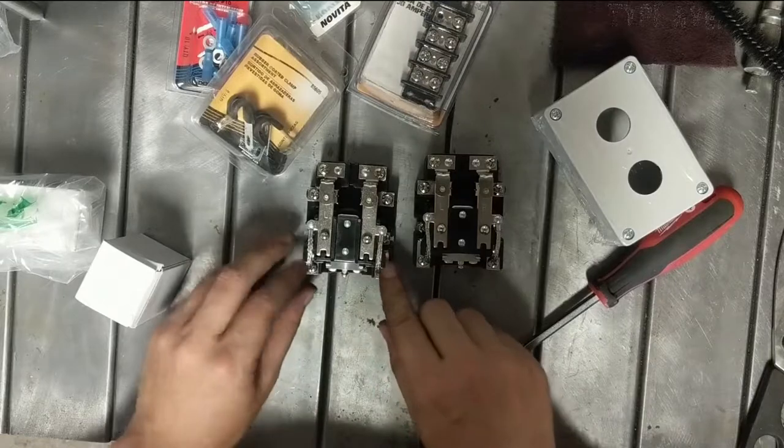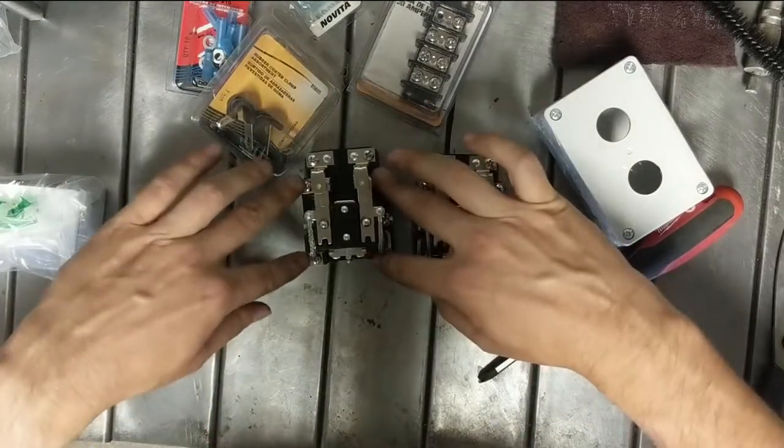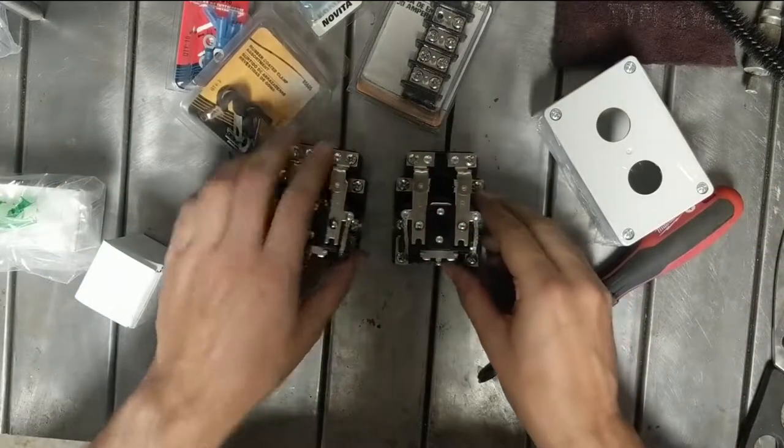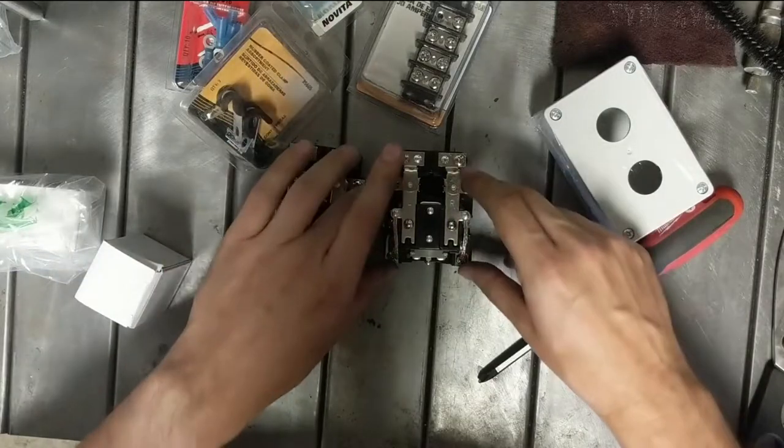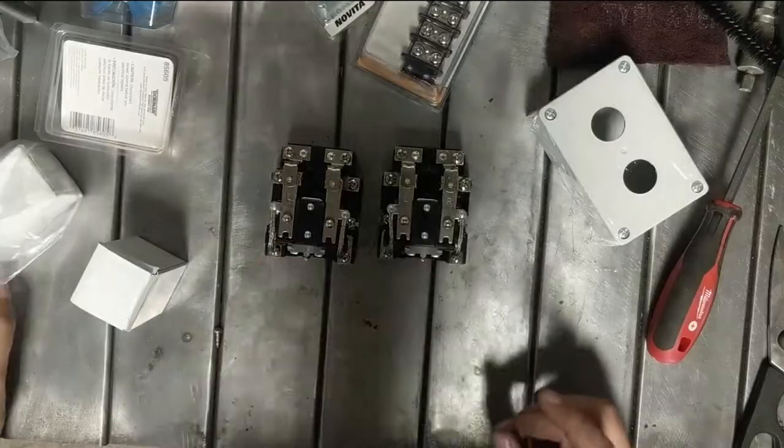What we're going to do is use the normally open contacts on one relay to make up our phase voltages, and we're going to use the combination of normally open and normally closed to make that reversing action.